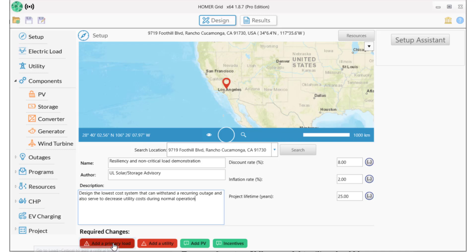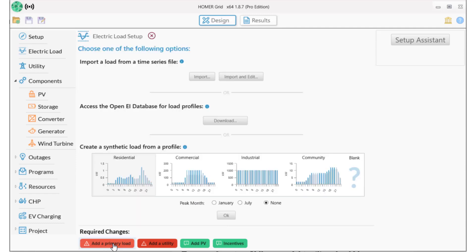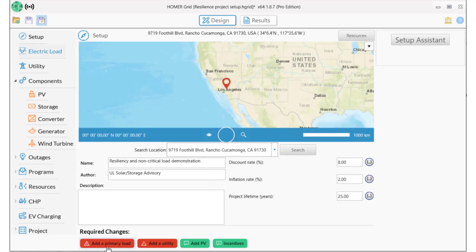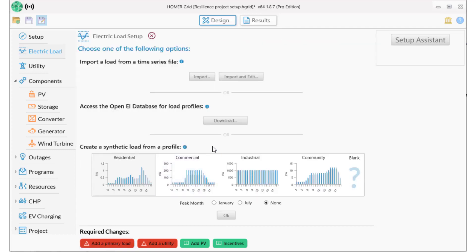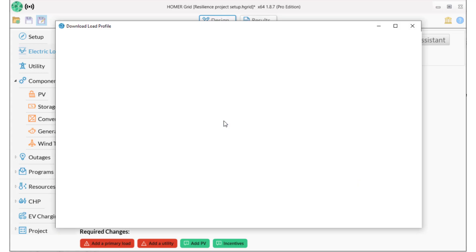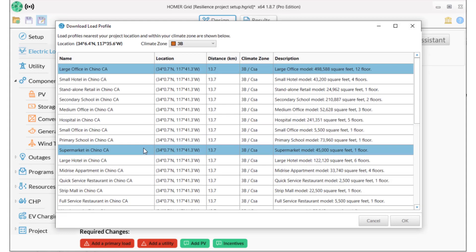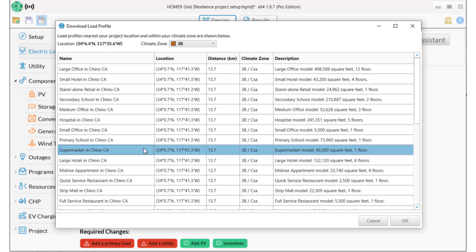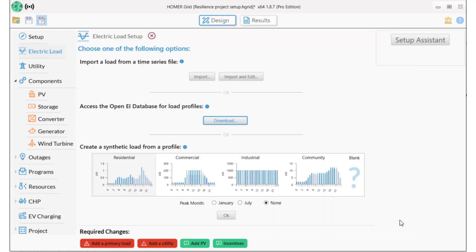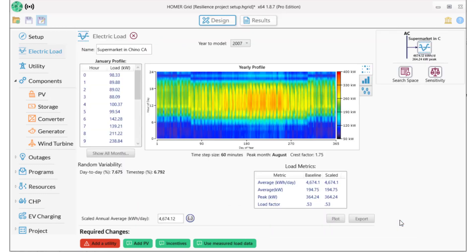This facility needs to keep its refrigeration units running during an outage at a minimum. I'll add a load profile using the OpenEI database. I select a supermarket in Chino, California. This is an average daily load of about 4,700 kilowatt-hours and a peak of 364 kilowatts.